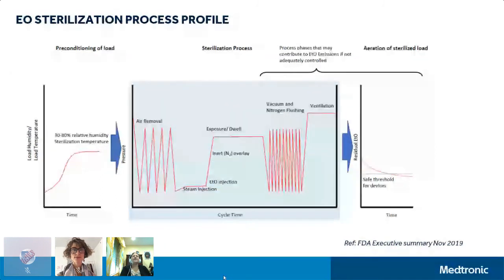And this requirement can also be traced back to one of the things pointed out by the earlier speaker on the spores, which are the most resistant bacteria to be killed. Somehow maintaining this humidity level tries to swell up the spores and then break them. And that's why maintaining a humidity level of 30 to 80% is optimum for sterilization effectiveness.